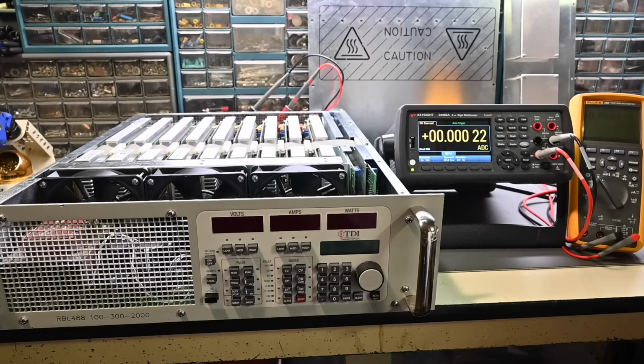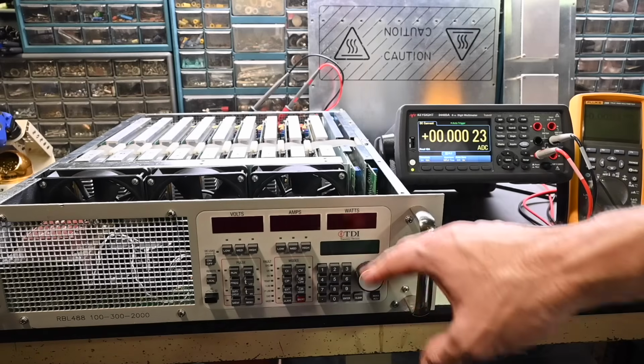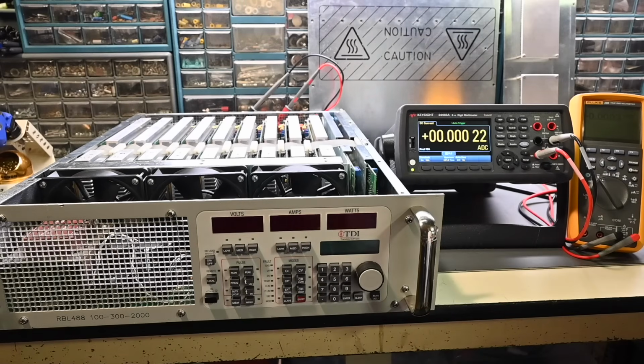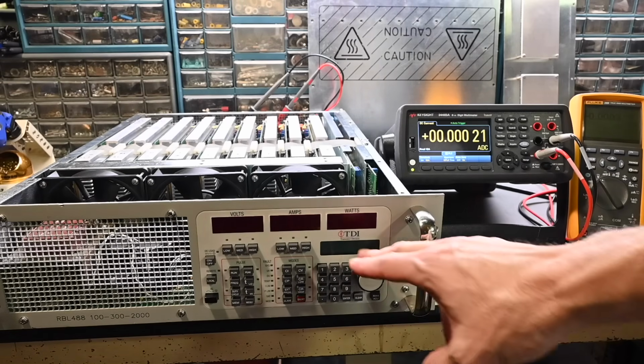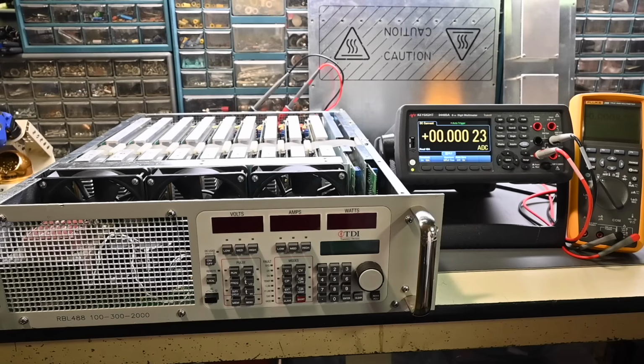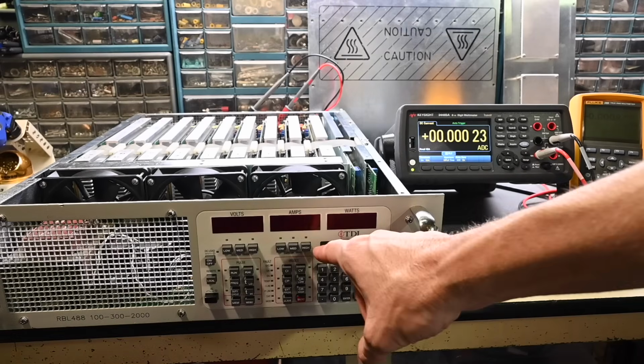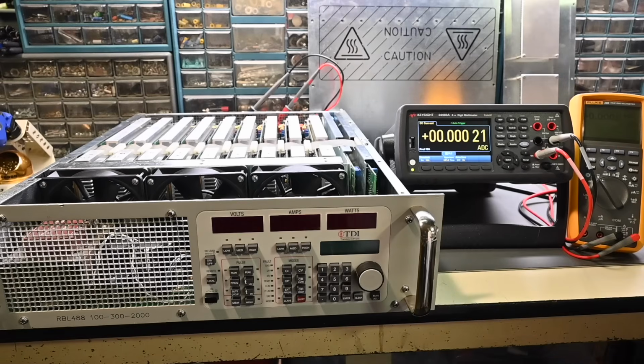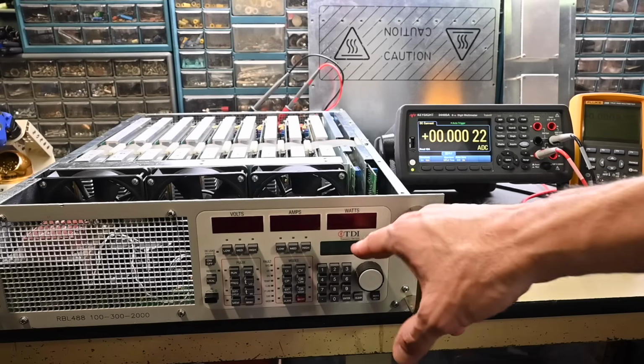Of course you wouldn't want to run the electronic load under high power dissipation with the covers removed because you don't have proper cooling on the heat sinks. But for this initial testing, the load won't be dissipating that much power, so it's perfectly fine to leave the covers off, and I'll return them as a final step. Now, I'm very pleased how these display windows cleaned up, especially this LCD window. It had a lot of film and kind of a scum that had built up on the inside of this window, and I noticed that when I powered up the electronic load initially, this LCD was very hazy and it wasn't very clear. So I'm pleased that the window was the problem and it wasn't something wrong with that display.